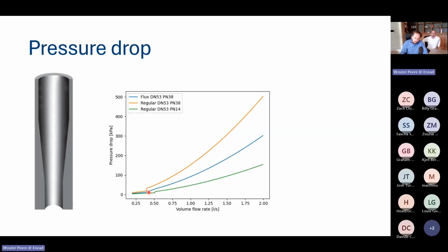The flux probe starts at the same point getting turbulence, and of course, because it's conical, it takes a while before the larger inner diameter gets turbulence. So that coincides with the PN14, and then it follows the same quadratic curve for turbulence pressure drop. But the most important thing for you is that you see that due to this conical design, our pressure drop is always in between the two extremes. And that's an interesting thing to notice.